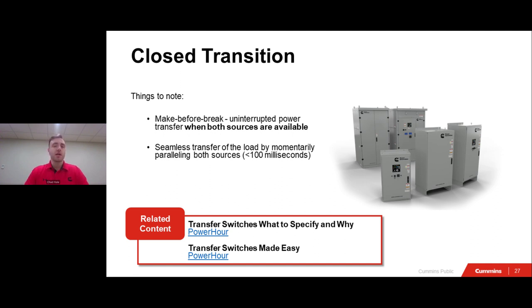So if transferring during a testing event, retransfer, or when both sources are live, then there will be no interruption of power. However, please remember, if only one source is available and there is a need to transfer, then there will still be an interruption of power to your loads. This most likely being that 10 seconds, especially if you're in an NFPA 110 type 10 system, when you have 10 seconds to get to the power to the load side of the transfer switch.